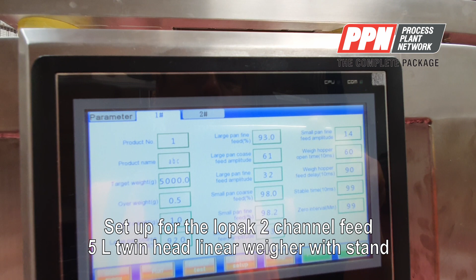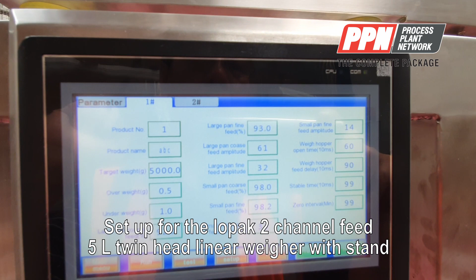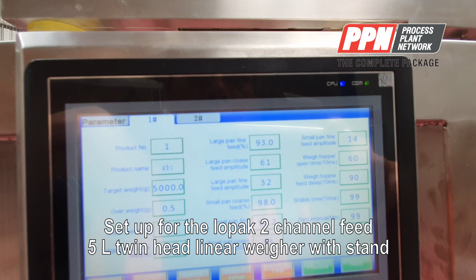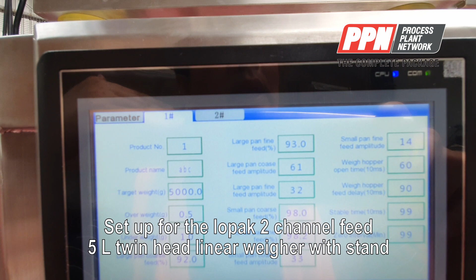We also have the hopper feed delay - that's the signal for the feed signal from the foot switch to tell when the bucket will open, or how long it gets delayed. Stable time is when the bucket weight stabilizes, it tells the program or computer that it has got the correct weight.